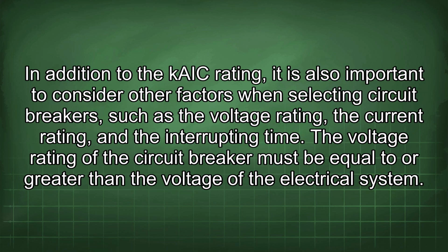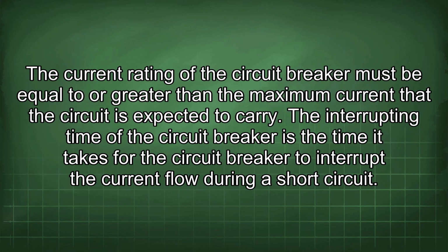In addition to the kAIC rating, it is also important to consider other factors when selecting circuit breakers, such as the voltage rating, the current rating, and the interrupting time. The voltage rating of the circuit breaker must be equal to or greater than the voltage of the electrical system.